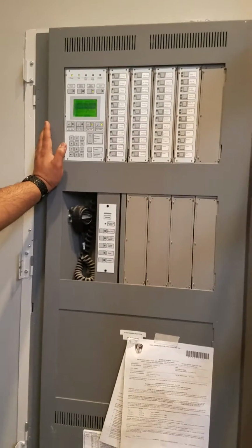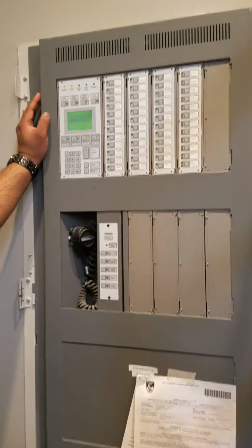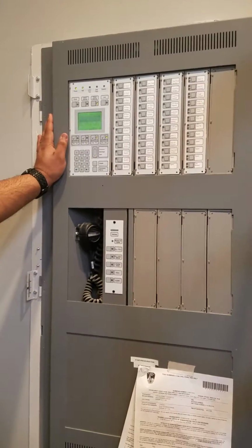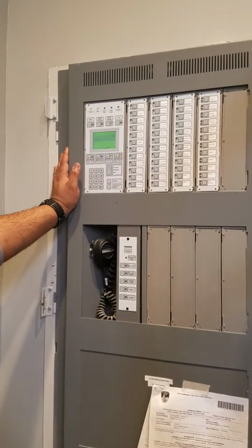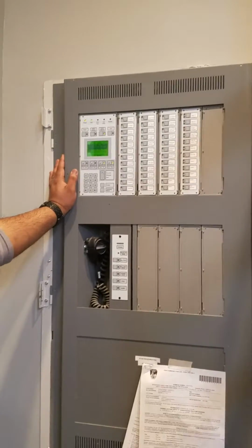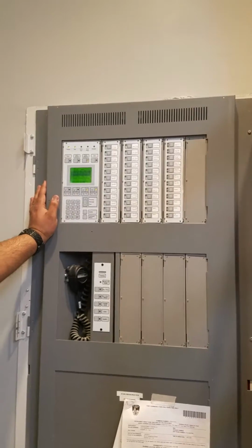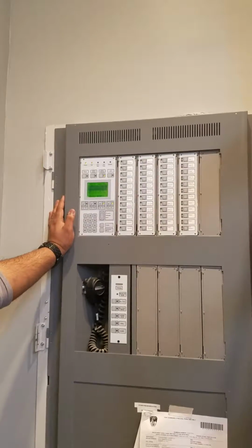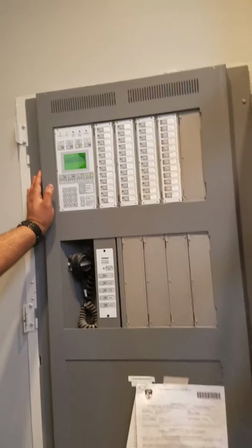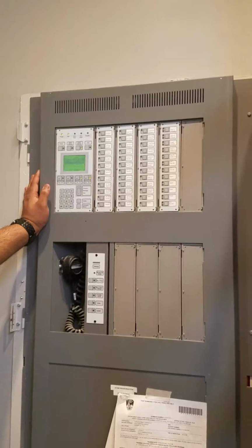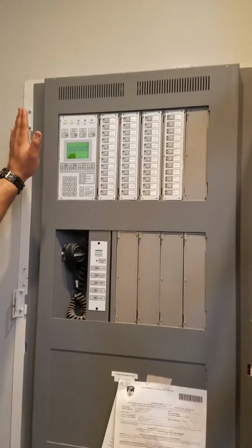Want to reset it when the guys leave, as long as you're offline, you're able to do so by hitting the reset button. Also keep in mind that because it's a new building and we're just coming out of construction and there's still construction going on, you're going to get nuisance alarms or false alarms, more than likely from the duct detectors, just because the dust travels in the air and kind of gets stuck in there. So when the fans kick on and are up and running, that dust travels and hits the duct detector, and it would cause false alarms. It would trip that duct into alarm.